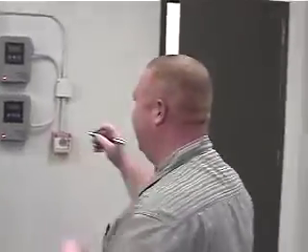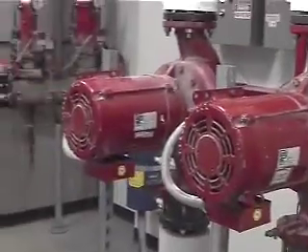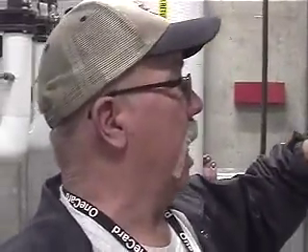If you keep going down, you have your two pumps right here. The way these pumps work is it's a lead-lag. We run one pump until it gets up to 90%, I believe. If it runs at 90% for a certain amount of time, it calls for the lag pump to run. Then that lag pump runs until, I believe, it gets below 30 hertz, or 30%, I'm sorry, and then the lag pump will drop off. So potentially you will keep both pumps running, but not always. On the drive, our lowest point is 15 hertz. 15 minimum. 60, of course.